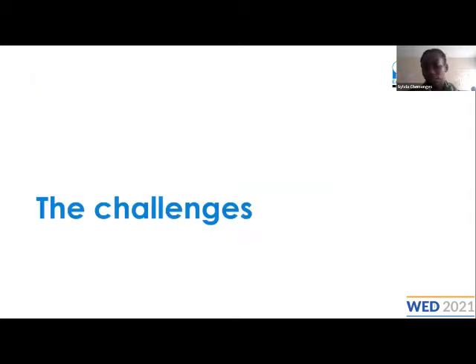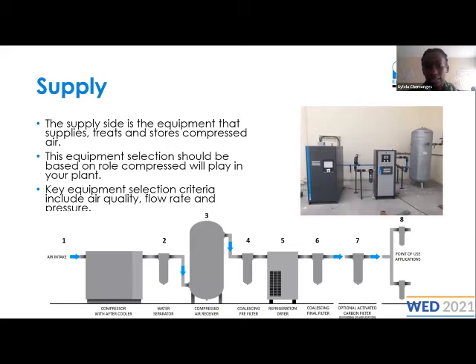So from that, I'm sure you can already think of some challenges that you might face when you're at site when dealing with compressed air. So we're going to look at the challenges when dealing with compressed air per subsystem. Starting with the supply side, compressed air is divided into 3 sections: the supply side, the demand side, and the distribution side. The supply side is where equipment is used to generate compressed air, to treat it, and then store it before it's distributed to the rest of the system and then consumed.